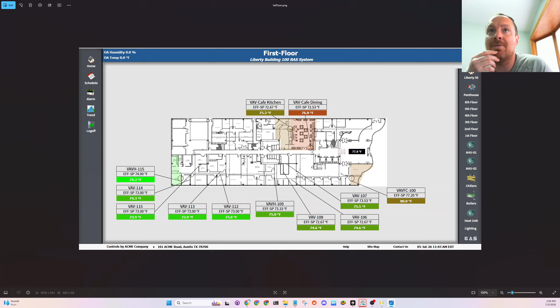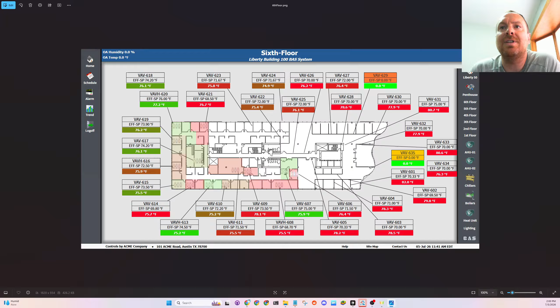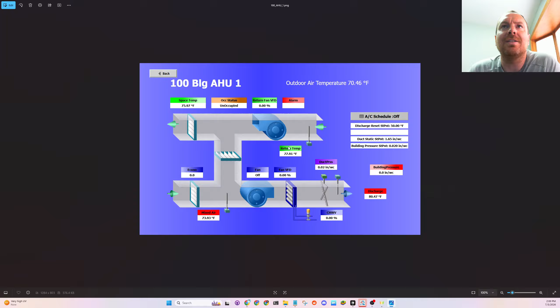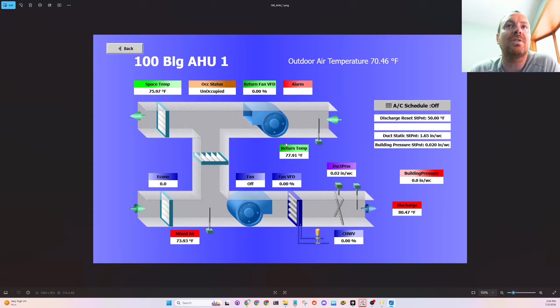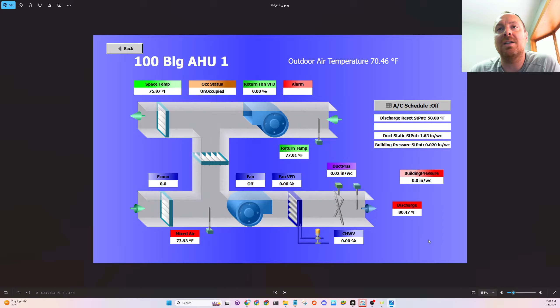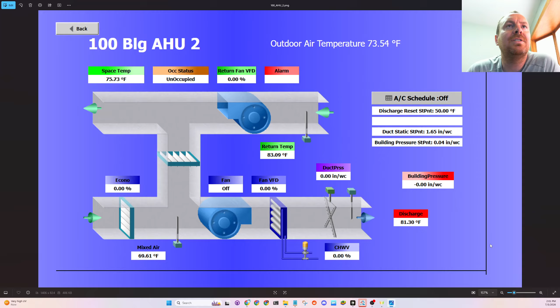So it's just an older VAV system, 2 air handling units feeding 6 floors. Nothing very fancy, just classic VAV systems, very ordinary air handling units with 1.65 inches of duct static pressure. So this is the duct pressure sensor right here. This is the variable fan with the VFD speed, and then this is mixing air, just classic return supply fan, mixing temperatures, return air temperatures, space temperature. I wonder if that's an average space temperature, and then leaving air temperature, cooling valve positions, and I think the VAV boxes have reheat coils. Same thing for the air handling unit 2.